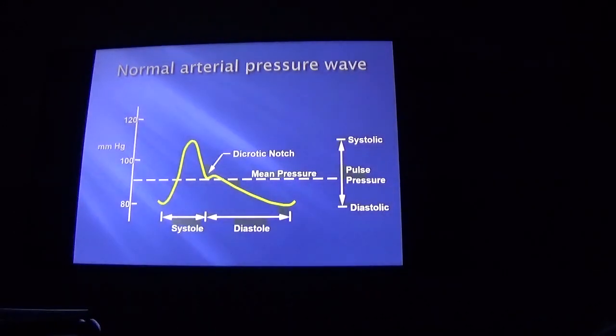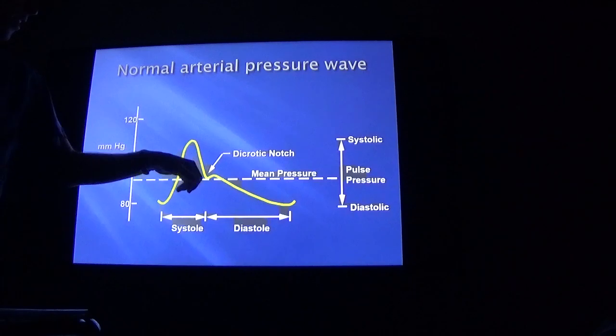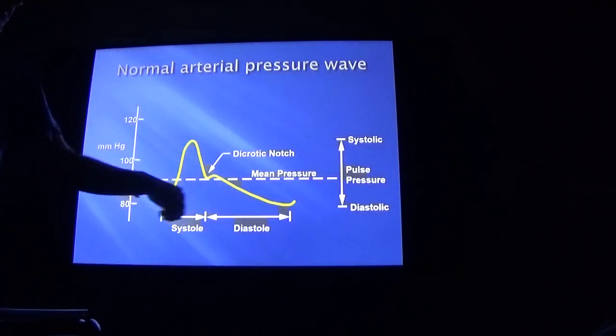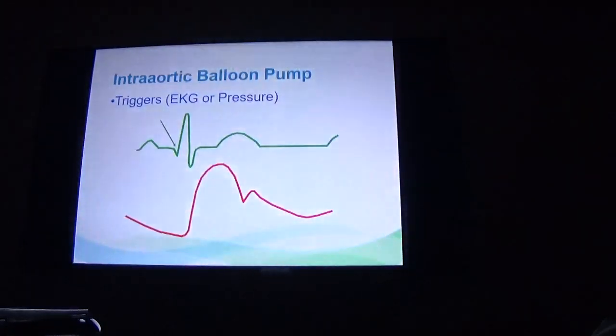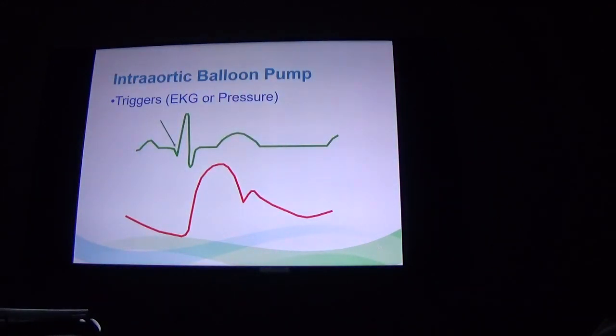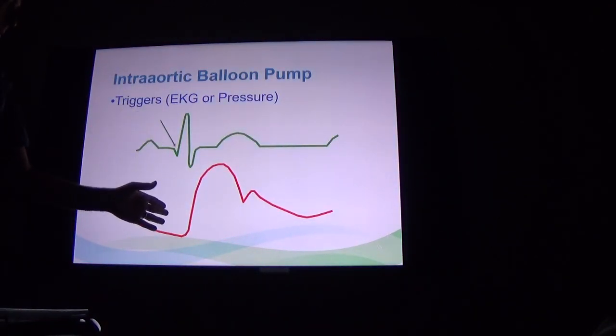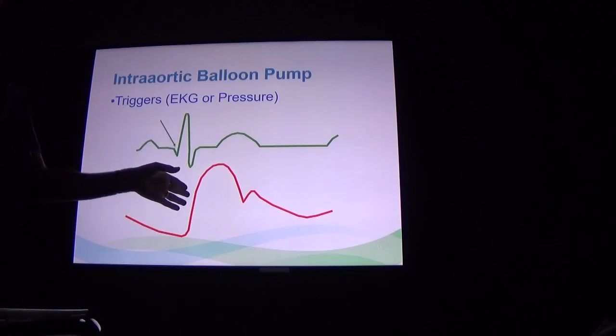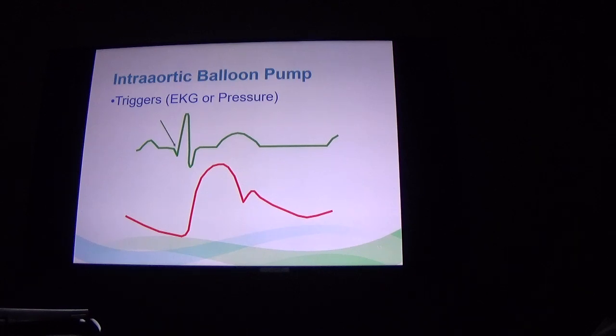Everyone remember this from med school? Specifically the arterial waveform. You see it on all your A-line tracings in the ICU. Specifically, you got systole, the dicrotic notch where the aortic valve closes, and then diastole. Well, this is kind of how the EKG plays along with that. Specifically, you have the R wave typically right before the systolic phase, because it takes milliseconds for that electrical current to actually generate the mechanical pressure. The EKG is the balloon pump's primary trigger.